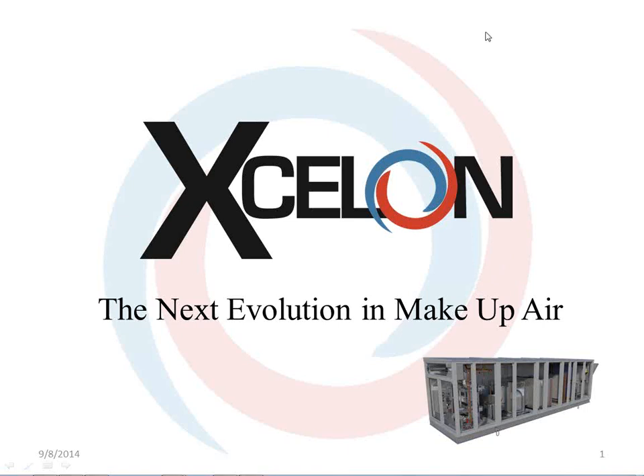All right. This is Xcelon's new makeup air unit. We're going to talk a little bit about the state of the industry right now as far as what's out there for efficiencies, some of the advantages and disadvantages, and limiting factors. Right now, the clamshell heat exchanger is probably the most commonly used heat exchanger out there. It is in the Xcelon product line. Each clamshell section is about 400,000 BTUs, and that 400,000 BTU figure is pretty consistent across all the different manufacturers out there.